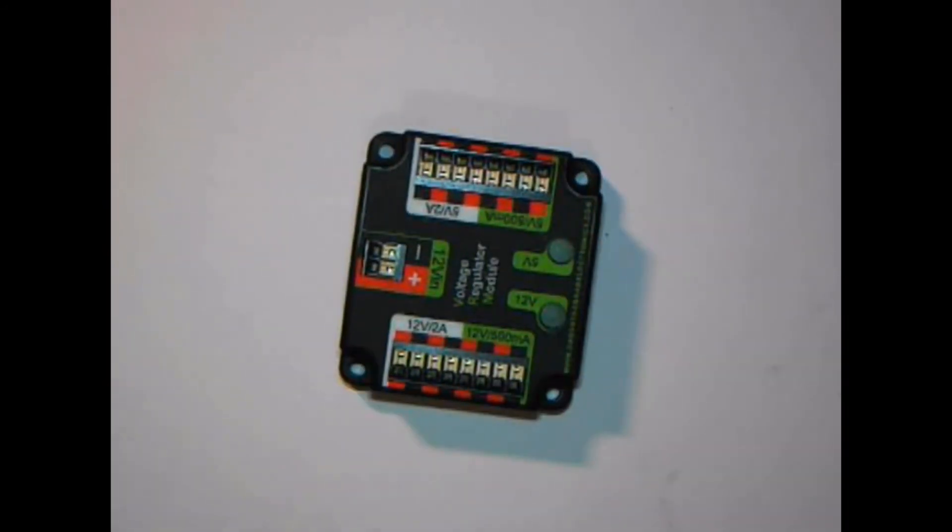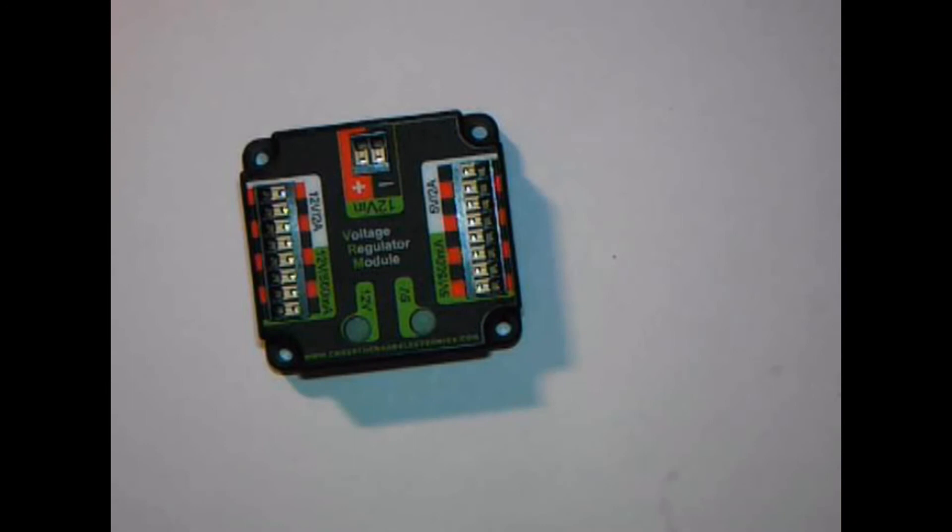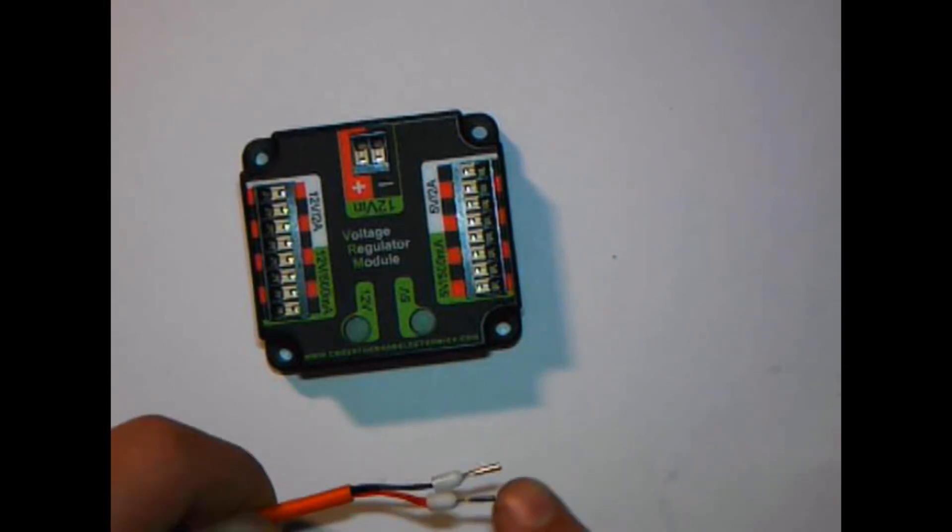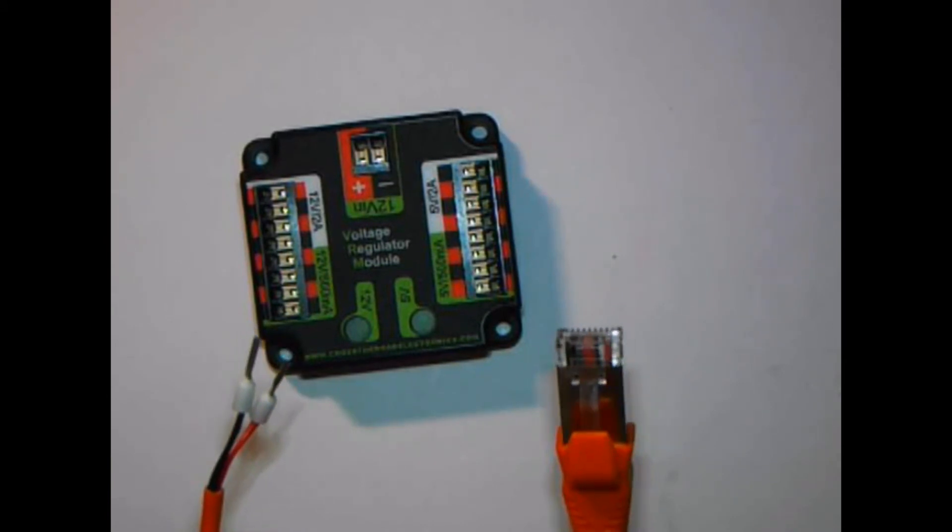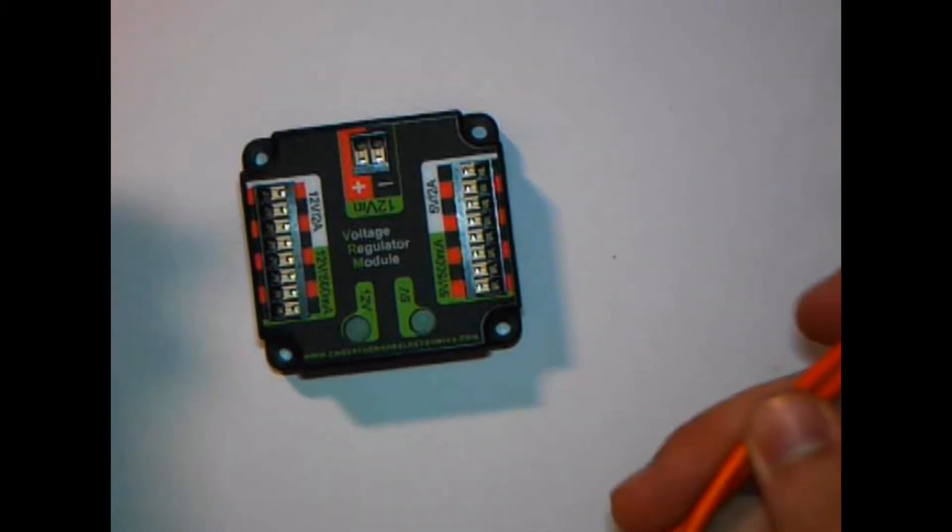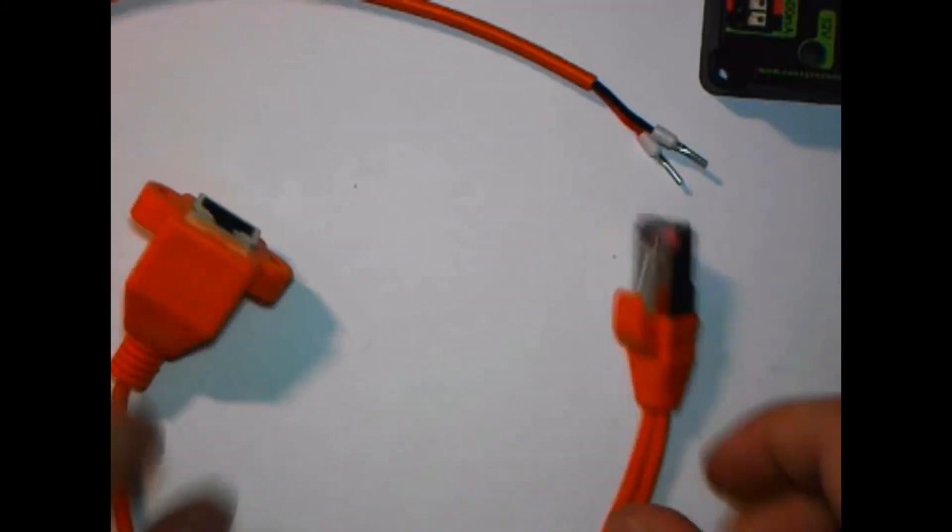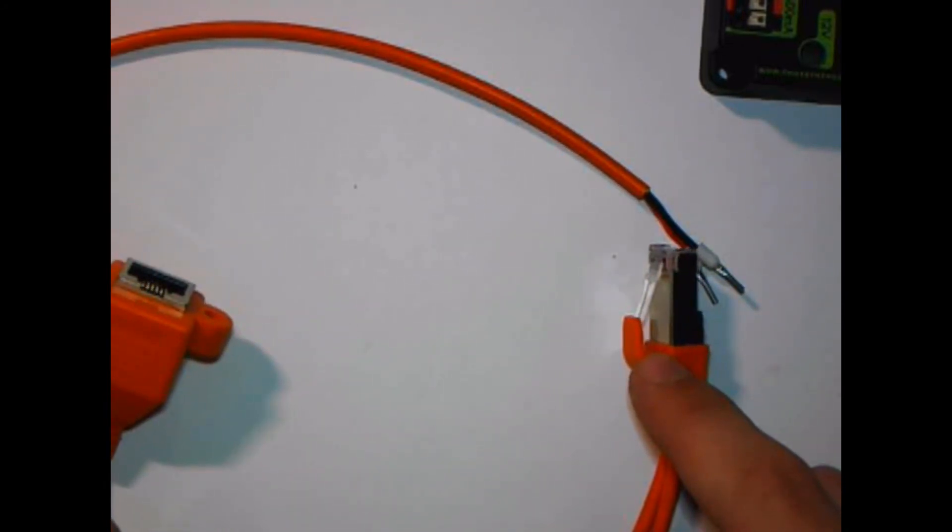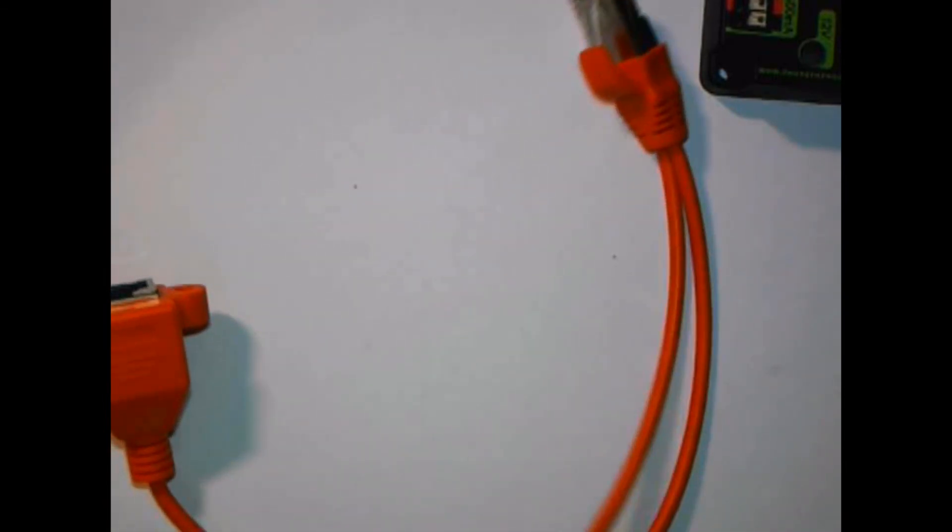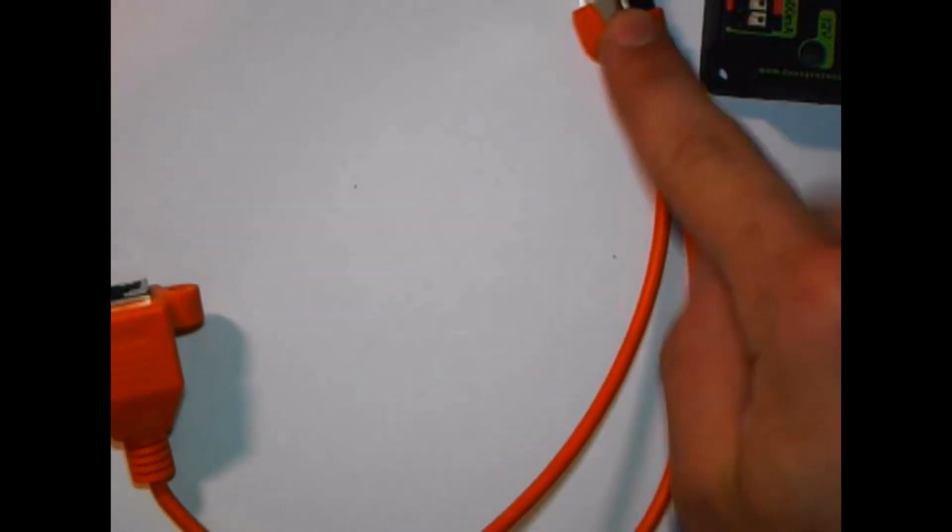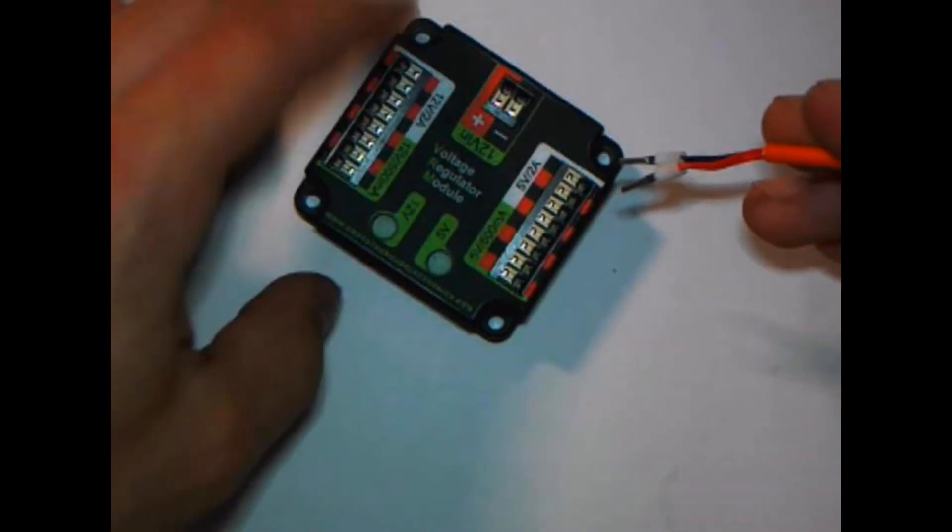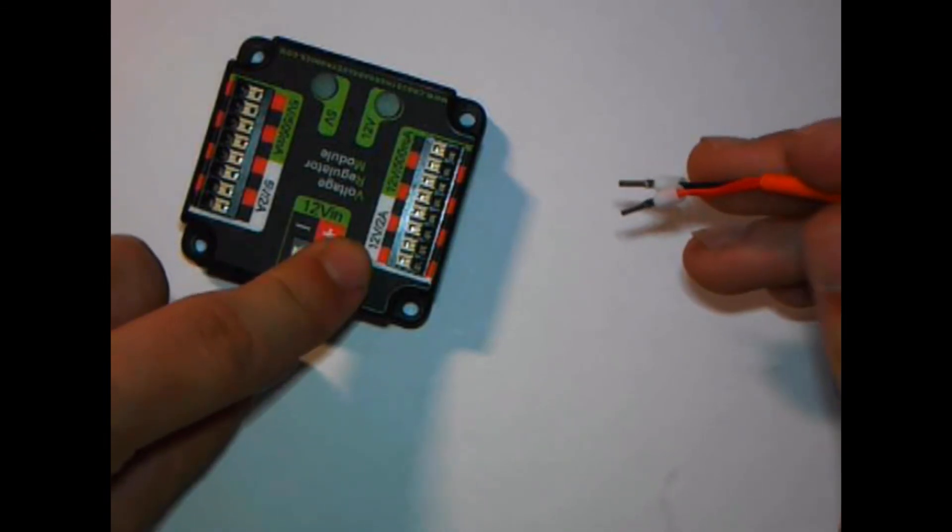Now, for the VRM, these are called Weidmuller connectors, and these are probably the simplest to use. Now you can use them with bare wire, but on our team we use ferrules because they're much stronger. So I'm going to demonstrate how, if you were to use PoE, how you would connect to set this up. So with PoE, it has two ports or two sides to the ethernet connection. And to figure out which side will go into the radio, you'll take the power wire and see where it goes. So this one goes into this side, so that'll be where we plug it into the radio.